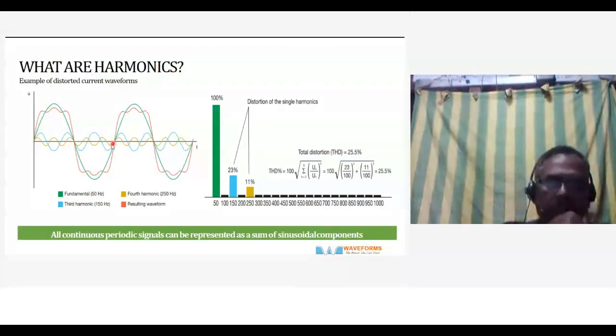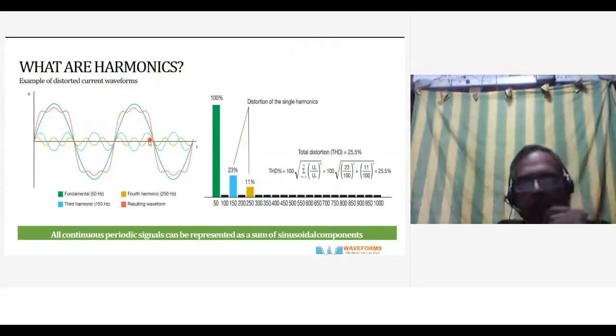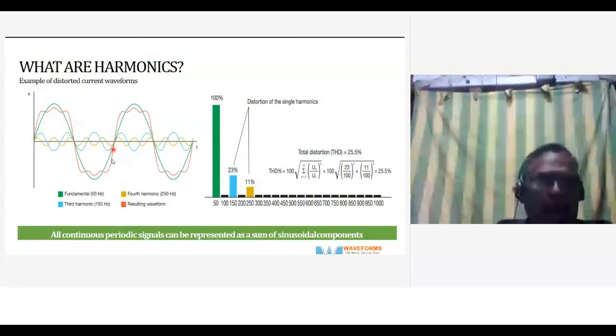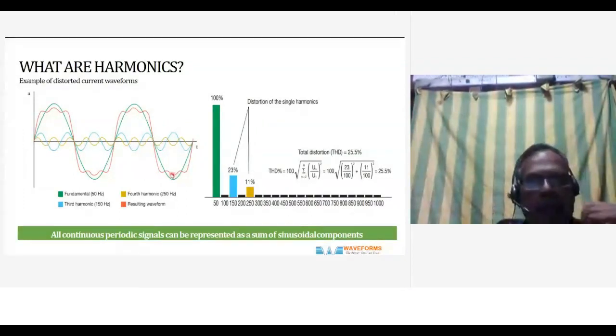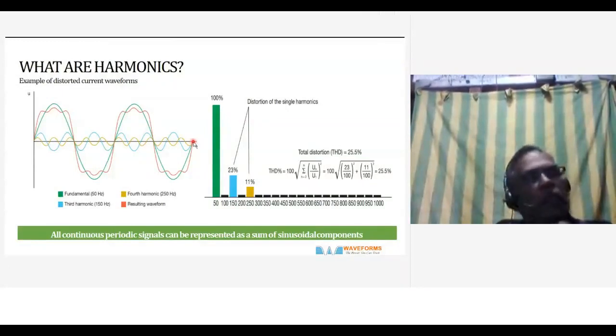It's written wrong, of course. It is actually the fifth harmonic. So like that, you have the seventh harmonic, which is about 350 Hz, and then the ninth is about 450 Hz. So it goes on continuously like that. These harmonics get superimposed on the sine wave, and the resultant voltage waveform will be in red. That is the ultimate waveform. Not only the current, the voltage also gets distorted, because when the current waveform gets distorted, the voltage also gets distorted.